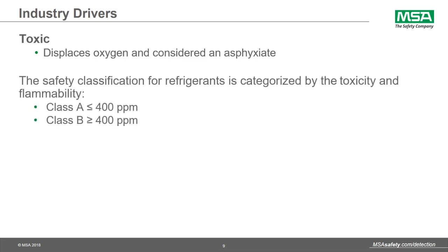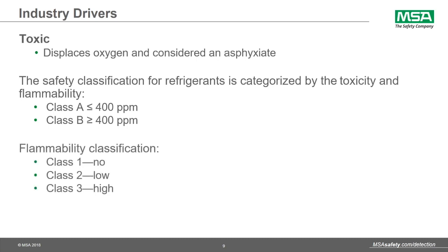I'll briefly review how a refrigerant is assigned a safety classification along with some other characteristics. The safety classification for refrigerants is categorized by the toxicity and flammability. Class A is a toxicity level less than 400 ppm, and Class B is a toxicity level greater than 400 ppm. And to classify flammability, there are three classes. Class 1 being that there's really no flammability present, and going to Class 3 being that there's a high flammability characteristic. It's also important to note that refrigerant is heavier than air, and that is a critical item when it comes to application.